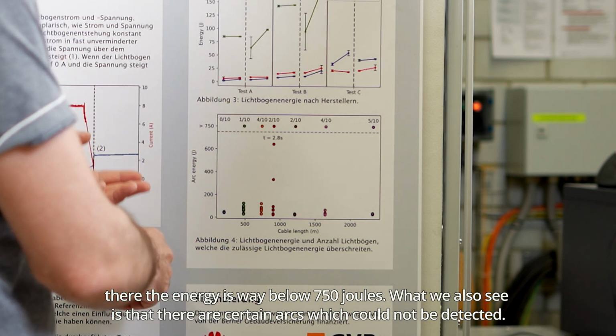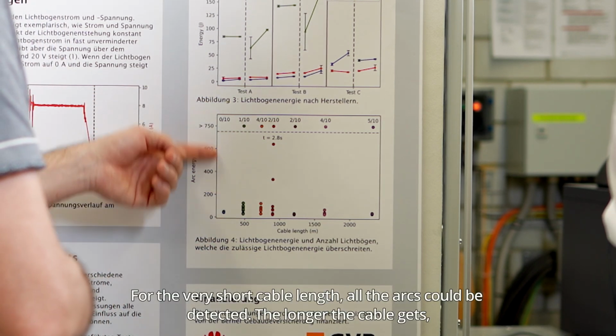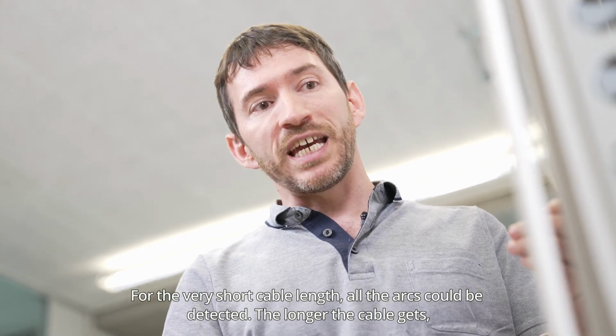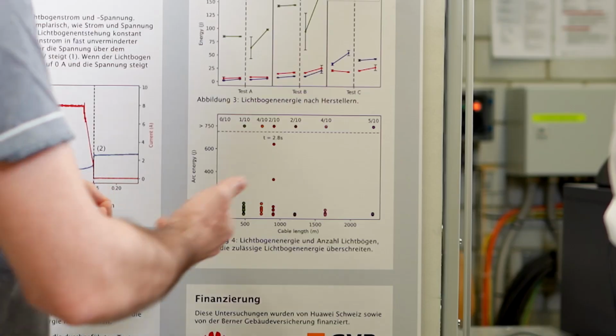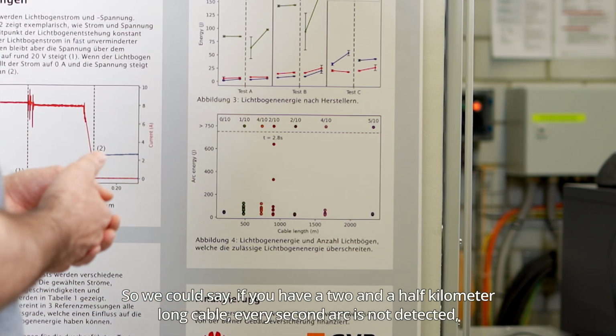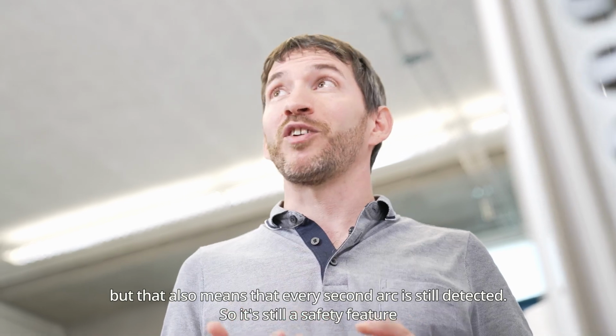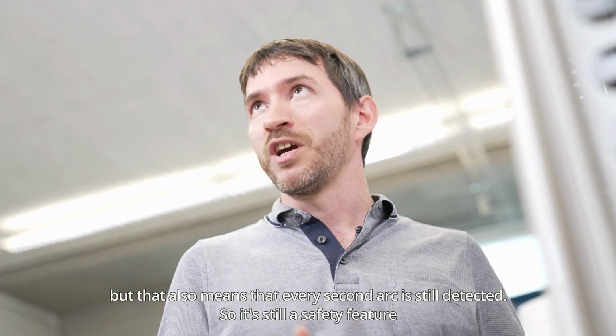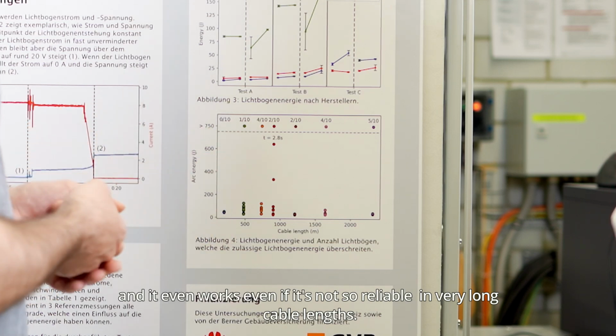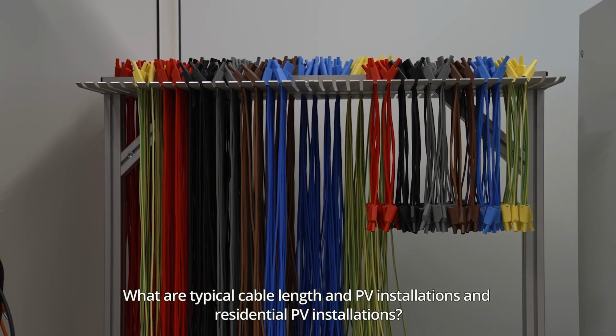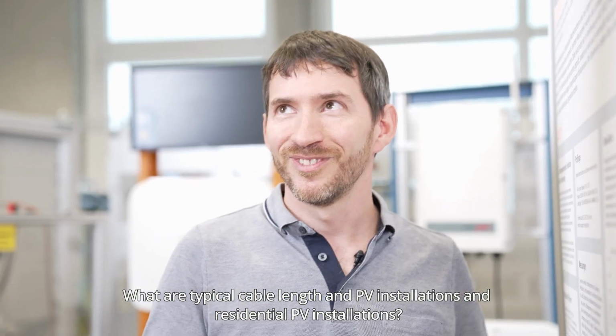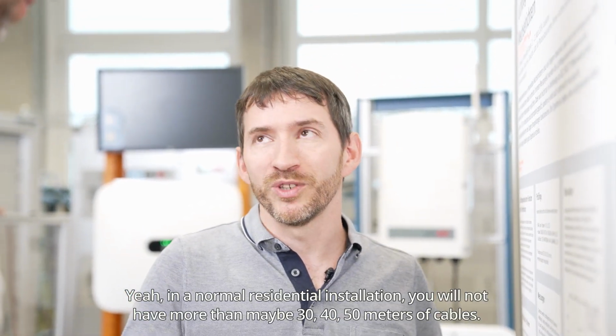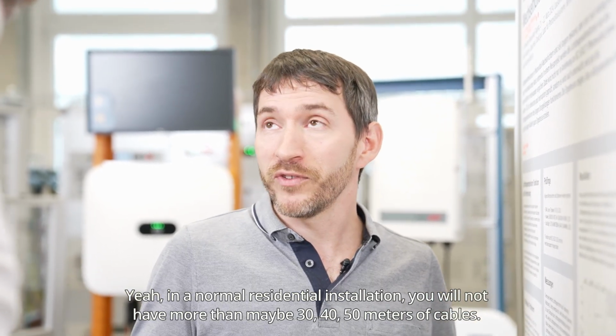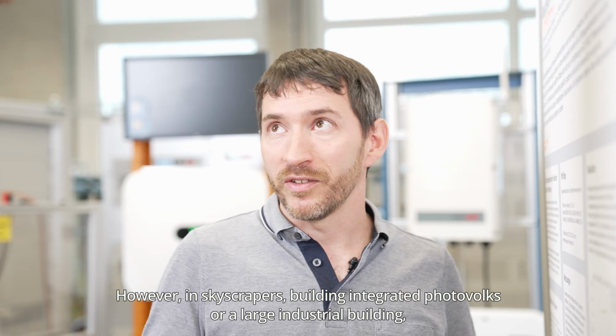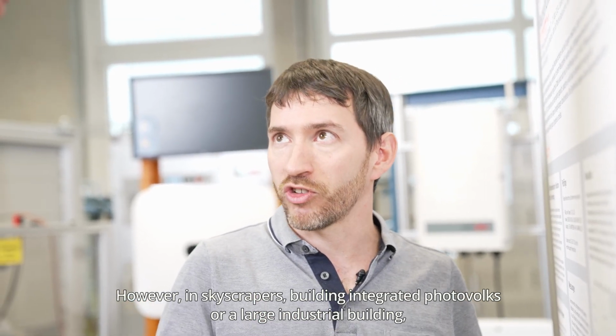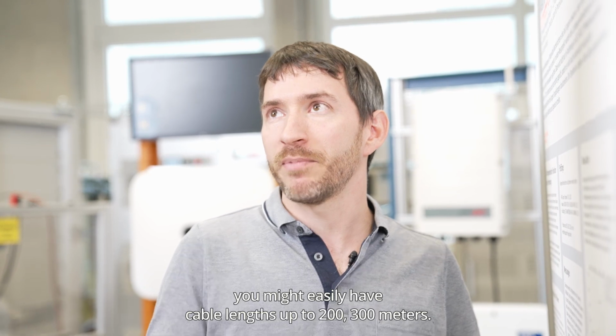What we also see is that there are certain arcs which could not be detected. For the very short cable lengths, all the arcs could be detected. The longer the cable gets, the more arcs were then not detected anymore. So we could say if you have a 2.5 kilometer long cable every second arc is not detected, but that also means that every second arc is still detected. So it's still a safety feature, and it even works, even if it's not so reliable, in very long cable lengths. What are typical cable length in PV installations, in residential PV installations? Yeah, in a normal residential installation, you will not have more than maybe 30, 40, 50 meters of cables. However, in skyscrapers, building integrated photovoltaics, or a large industrial building, you might easily have cable lengths up to 200, 300 meters.